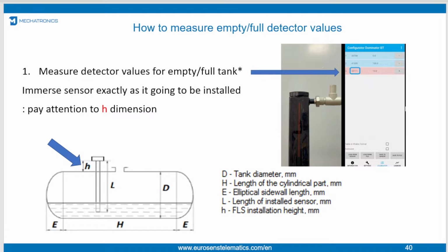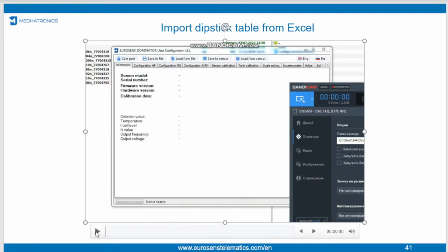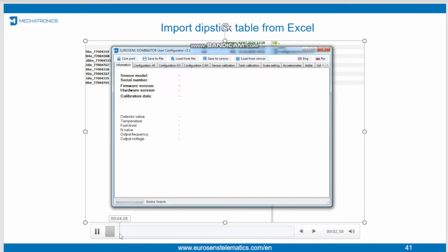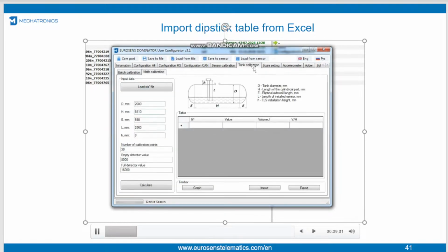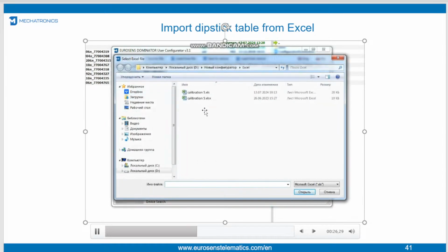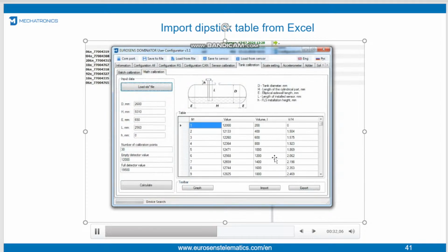So now we are ready to make the calibration table. How it looks in the configurator. So you open the calibration tab, math calibration. Here is a button, load Excel file. Before that, we need to set up the empty and full detector values. We obtained them just now during calibration in the tube, and load the file. And your calibration is ready. You can save it into the sensor, and you don't need to make a time-consuming tank calibration.